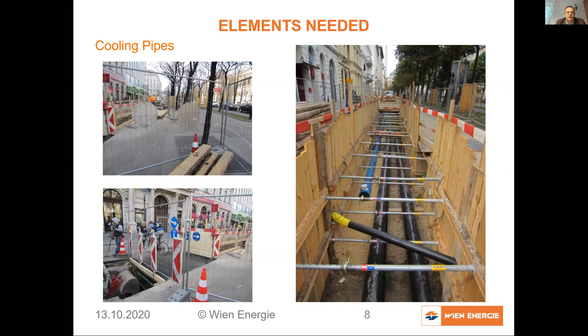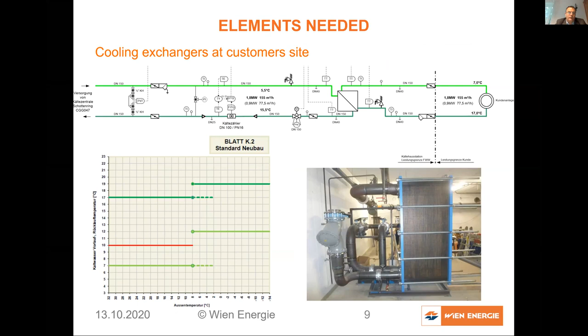What we need is a cooling exchanger at the customer side, which provides the cooling to the customer. What the customer or we provide is the way the cooling comes into the building, into the flat or office — in most cases some kind of fan coils, cooling registers, or ceiling cooling, because most of the time district cooling is for office buildings, not flats. But we see cooling in flats growing very fast, so we look more and more into underfloor heating also for use as cooling.